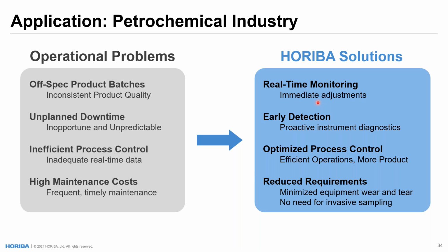Real-time monitoring allows for immediate adjustments. So if, for example, a refinery has our analyzer read into their advanced process control system, this allows for immediate adjustments in their blending operations, for example, to help regain the specs that they need for the blend that they're looking for. Likewise, our analyzers offer early detection with proactive instrument diagnostics. So for example, if laser power starts dropping, it will immediately alert the end user, turn that laser off, and kick the redundant laser on and keep it on to ensure that a laser failure would never bring your system down, as we can ship you another one. Likewise, as I've stressed for sure, the optimized process control allows for more efficient operations, more product, and overall, we solve a lot of problems by just reducing the requirements that a refinery needs to achieve the data that they want.